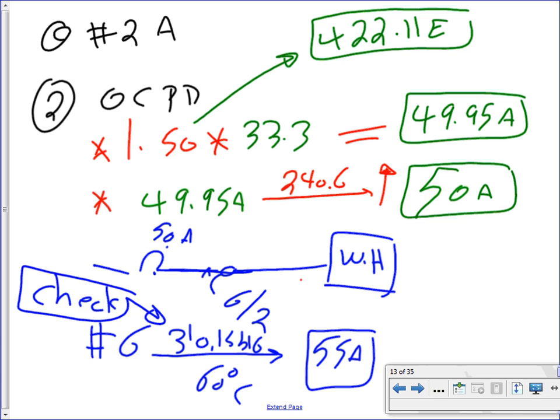Check if your conductor can carry. So, I have a 50 amp circuit breaker protecting a number 6, and this number 6 can carry 55 amps. Am I okay? Yeah. If you end up with 40 here, you have two options. Either you lower the overcurrent protection device to 40, or you have to up your conductor. Do you guys hear me? So for example, say I use number 8. How much can number 8 give you, guys? 40 amps. Number 8, 310.15(B)(16).